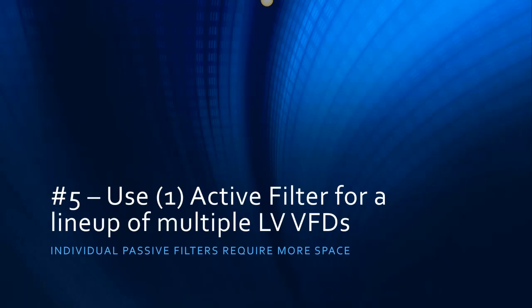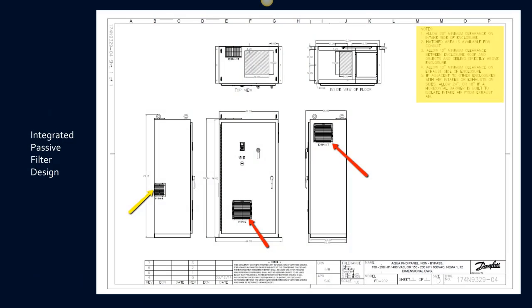Okay, here's one I've run across a few times now in the past couple of years. VFDs, in order to meet IEEE 519, usually require some sort of filter. And we, meaning Danfoss, and the other manufacturers like Yaskawa and I believe Eaton and Schneider, offer pre-packaged enclosed drives with a transformer, a reactor already installed into the cabinet that acts as a filter to try to get the total harmonic distortion to less than 5% and therefore meet IEEE 519. And this is how we do it.